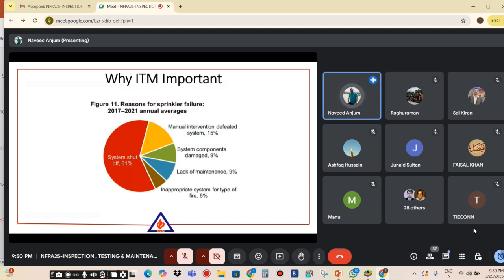I have got this record from NFPA, and this is from 2017 to 2021 annual averages. The reason for 61% of sprinkler failures is the system being shut off. I have visited almost 100 plus different industries, and I have noticed that mostly they don't have tamper switches on their main valves. Either we have a tamper switch on our main valves, or we lock them in the open position. These are the two options. Otherwise, in case of emergency, there might be a chance that the valves are already closed. So in this scenario, the sprinkler will not be working.